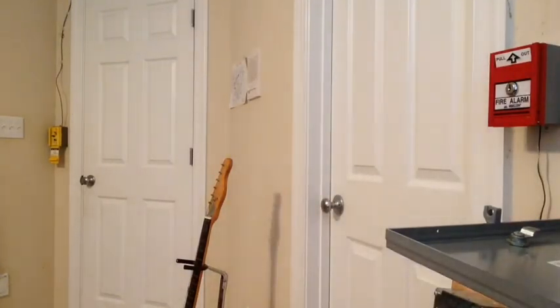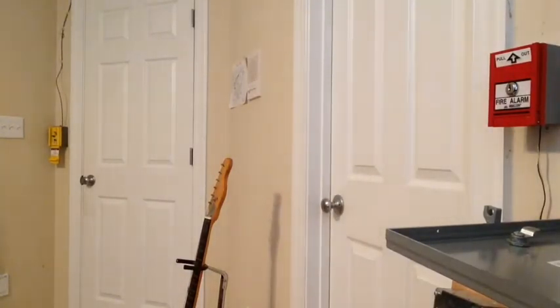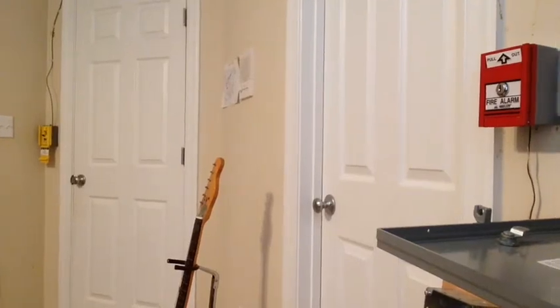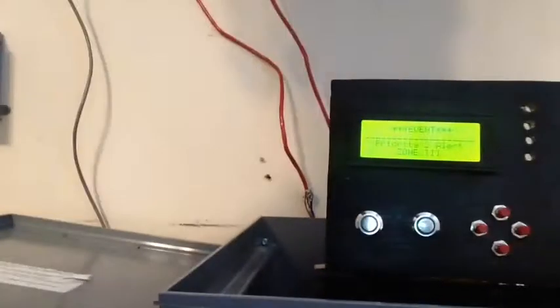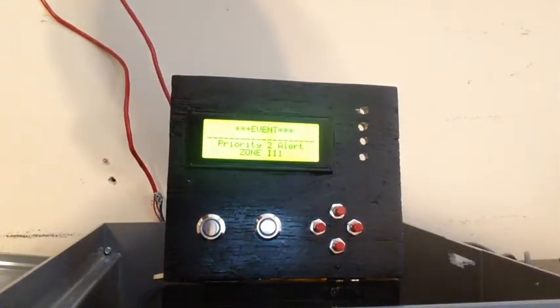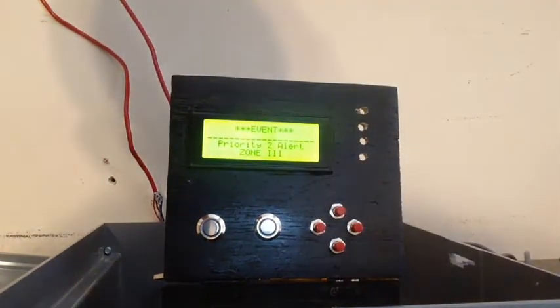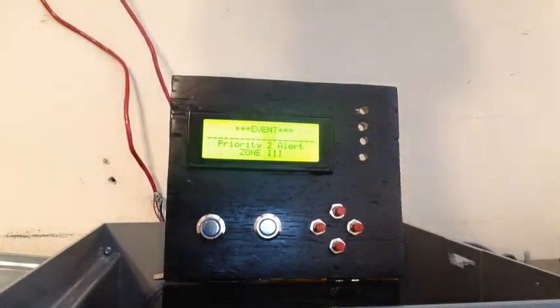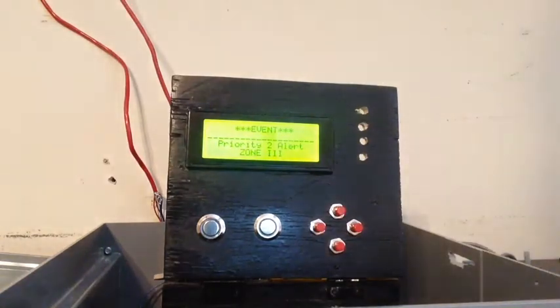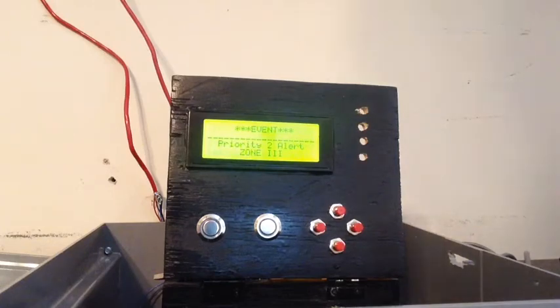Now you'll notice that the alarms are not sounding. Why is that? Let's have a look at what the panel says. That's right, that zone 3 is set as priority 2. I chose to custom label it priority 2.